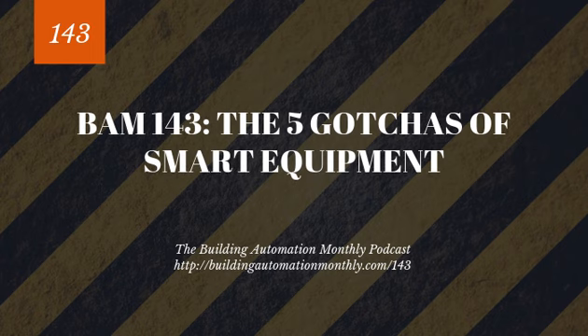Now, I want to go through a couple things real quick because I kind of just flew by that. An upstream system is something that supplies your system. So an upstream system from a VAV air handler would be like a chiller that supplies a chilled water coil, or a boiler that supplies a hot water coil. A downstream system is a system that is dependent on that specific system. So a VAV box would be dependent on a VAV air handler. Thus, VAV box would be a downstream system. A cooling coil is dependent on sometimes a secondary chilled water pump and mixing valve, sometimes the actual chiller itself. And so those are dependent systems.